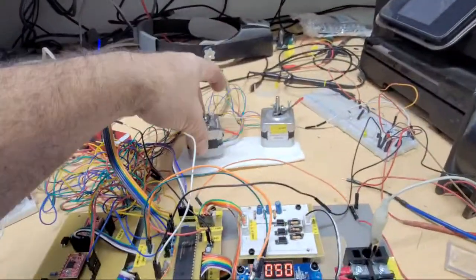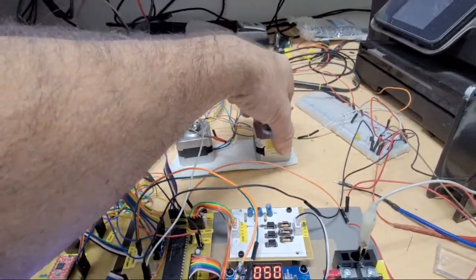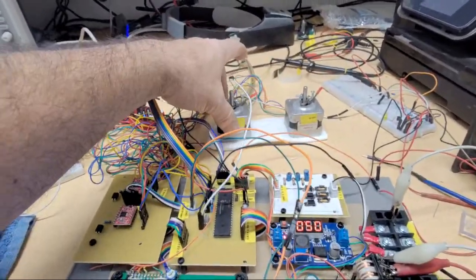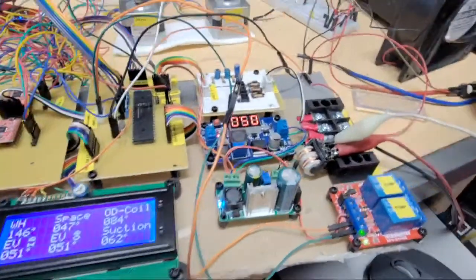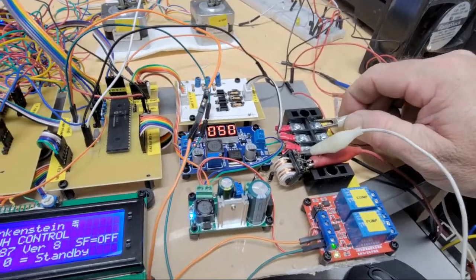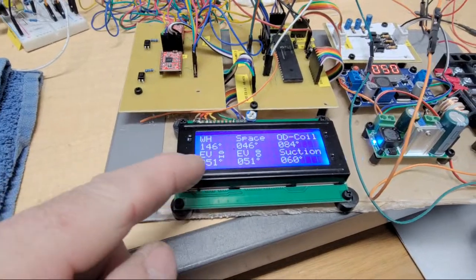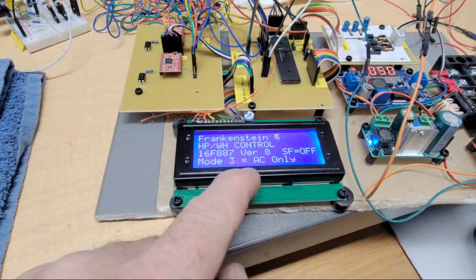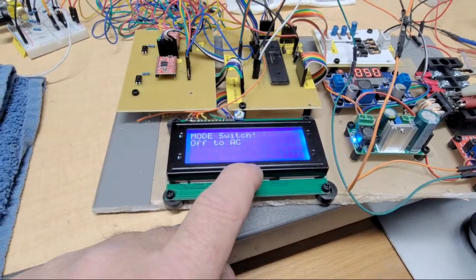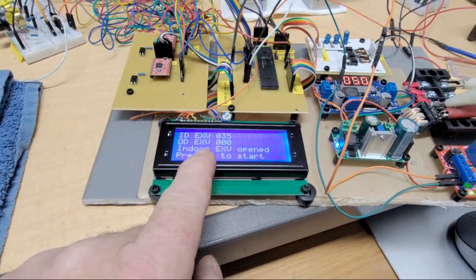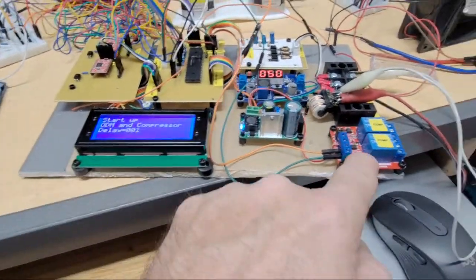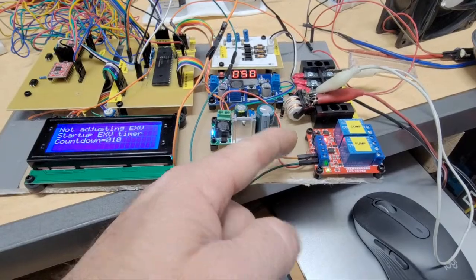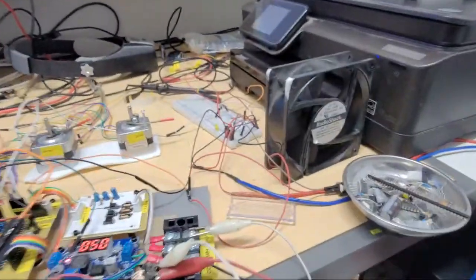And I was just homing the EXVs, which are just regular steppers here. Oh, and then I gotta turn this on right there. Yeah, so it's on standby mode. If I want to put 24 volts to the air handler only, as it cycles through, it's reading the sensors, thermistors, and it's going to see AC only. Then the next part of the subroutine, what's it doing? Oh, it's going from off to AC, and it just opened that and is doing the countdown. It's going to turn on the compressor relay, which it just did, and that fan should be running too.